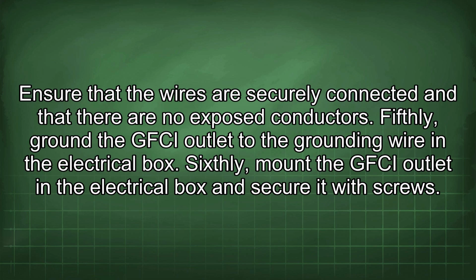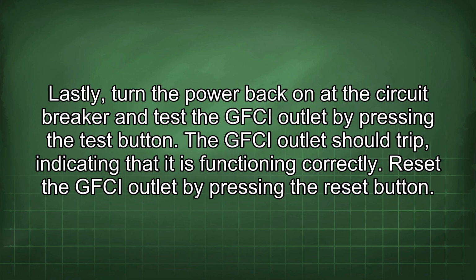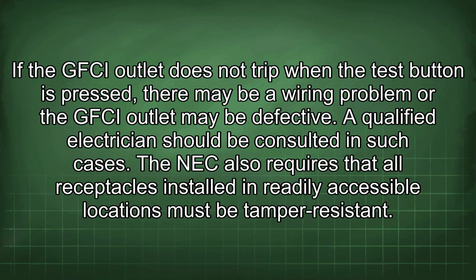Fifthly, ground the GFCI outlet to the grounding wire in the electrical box. Sixthly, mount the GFCI outlet in the electrical box and secure it with screws. Lastly, turn the power back on at the circuit breaker and test the GFCI outlet by pressing the test button. The GFCI outlet should trip, indicating that it is functioning correctly. Reset the GFCI outlet by pressing the reset button. If the GFCI outlet does not trip when the test button is pressed, there may be a wiring problem or the GFCI outlet may be defective. A qualified electrician should be consulted in such cases.